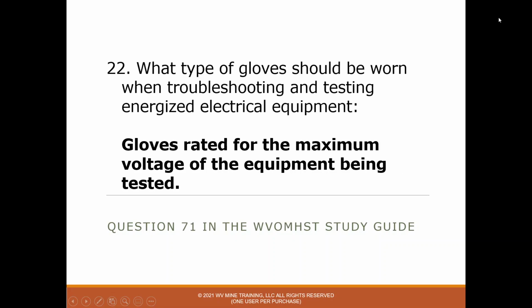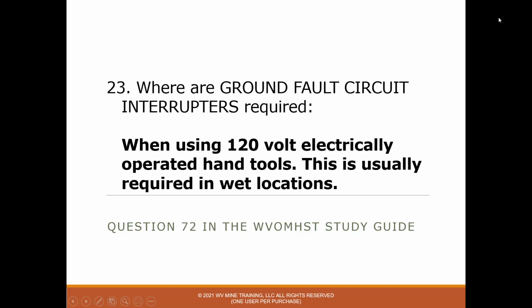22, what type of gloves should be worn when troubleshooting and testing energized electrical equipment? And the answer to that is gloves rated for the maximum voltage of the equipment being tested. Again, you're not allowed to work on energized equipment. You can only troubleshoot and test. So you wear gloves rated for the maximum voltage that you would encounter. You troubleshoot and test, and as soon as you determine what's wrong with the piece of equipment, you should de-energize, lock and tag it out, and make your repairs.